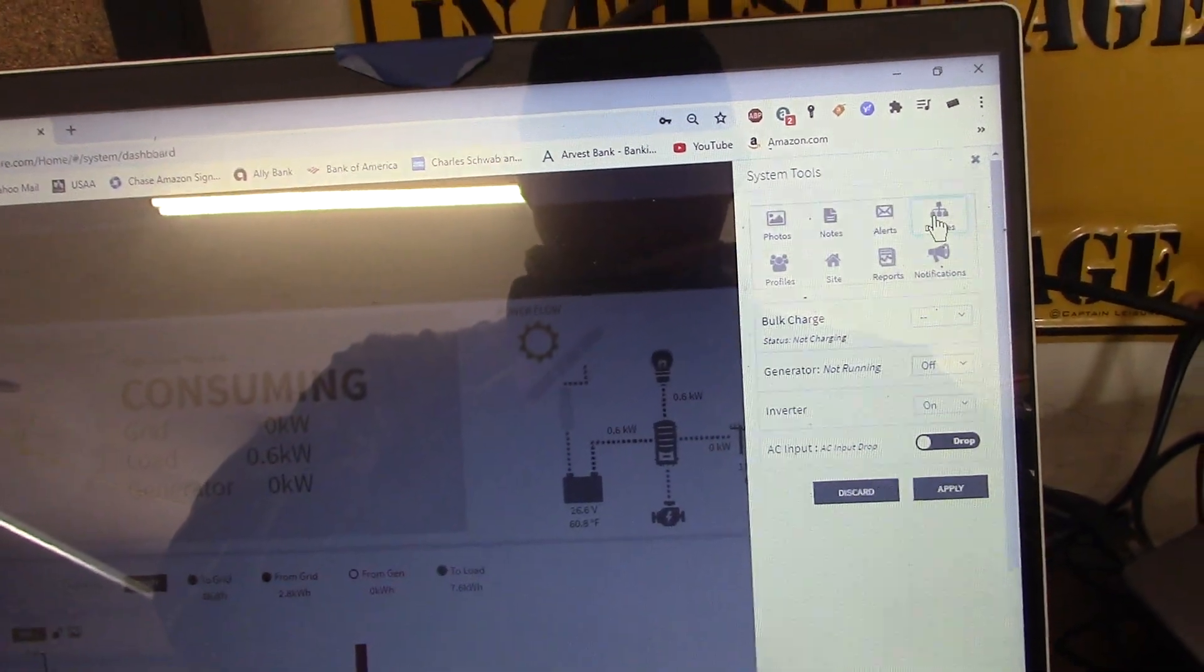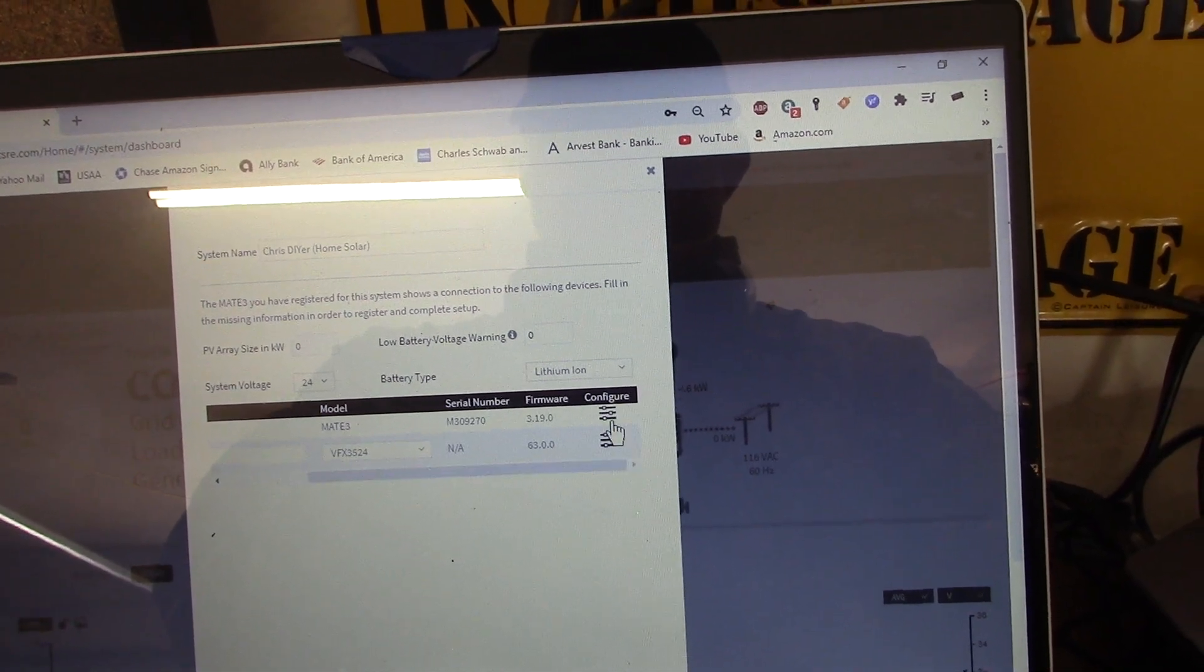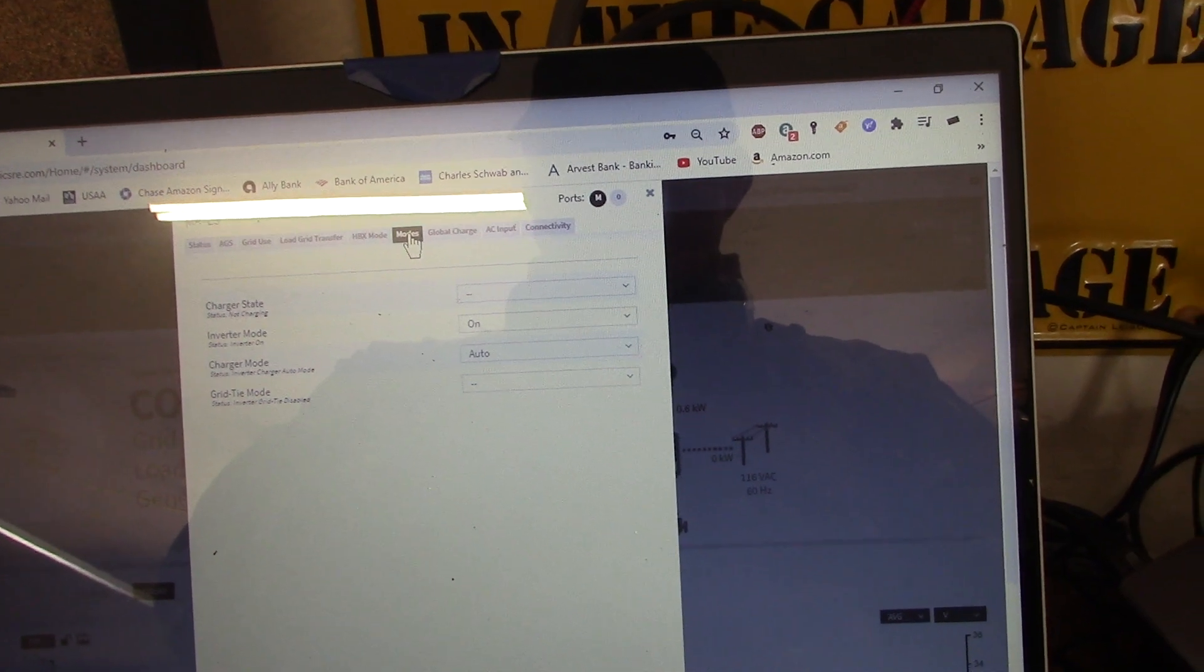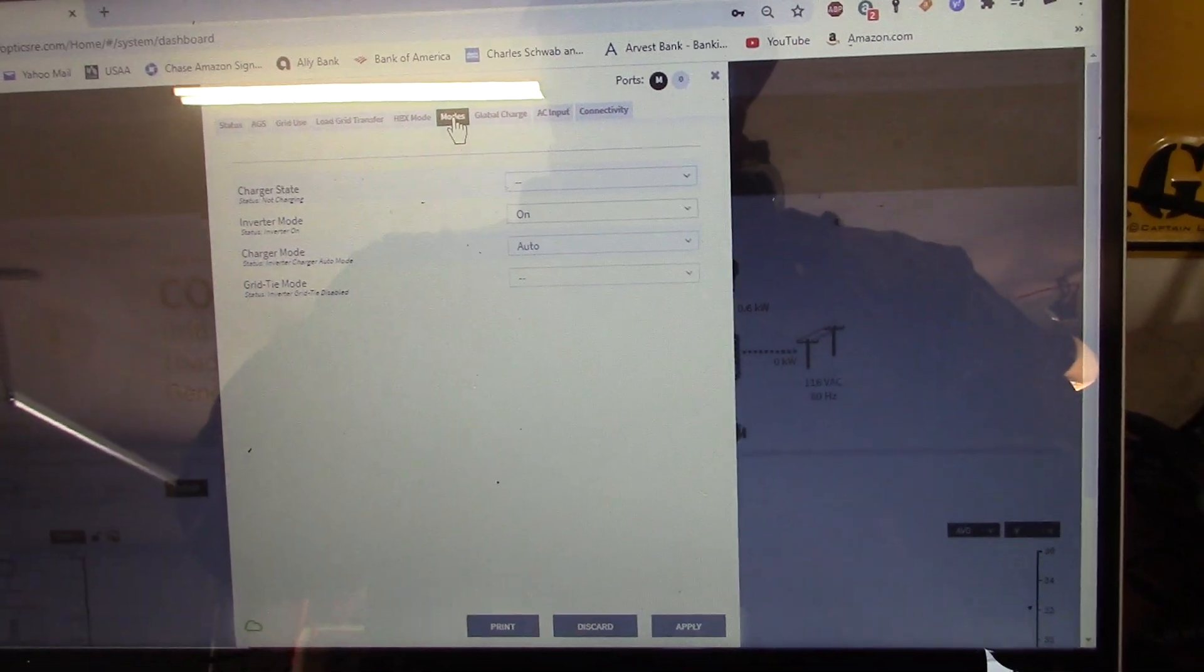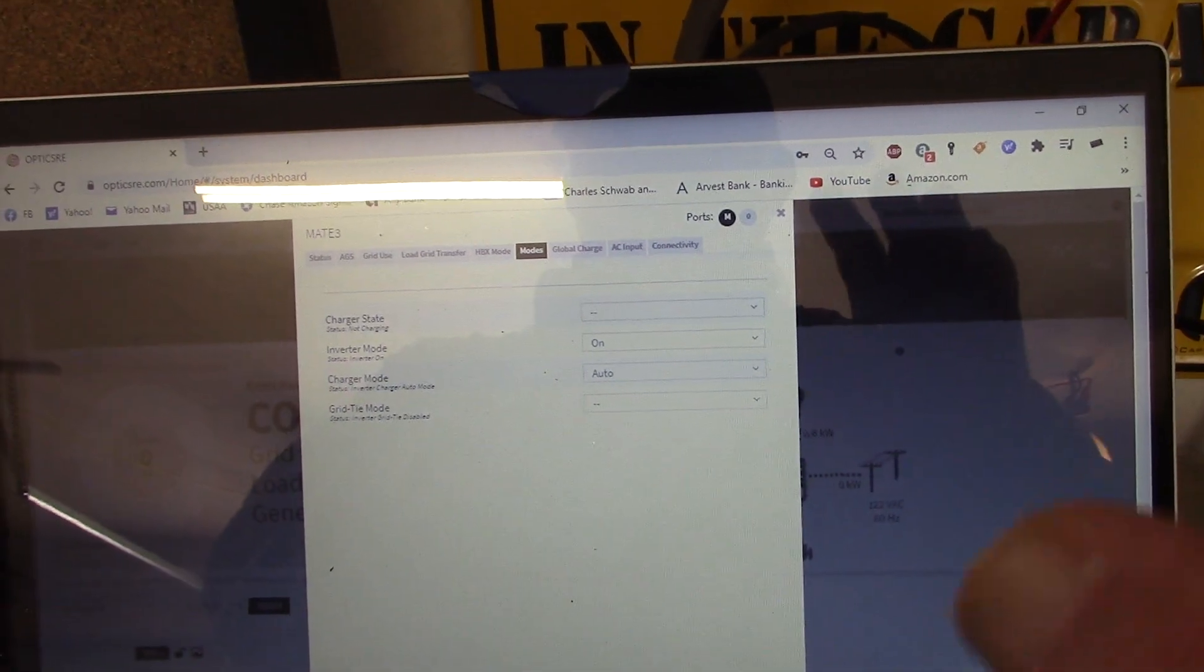If you go to devices, you got to go into Mate 3 here to configure your mode. I don't know if you can see that or not. But right down here this had no default on here at all. Charger mode was blank. And it's got to be in auto mode. So both the inverter and the Mate 3 have got to talk to each other.